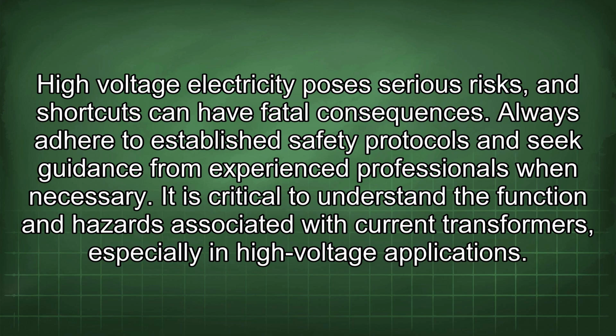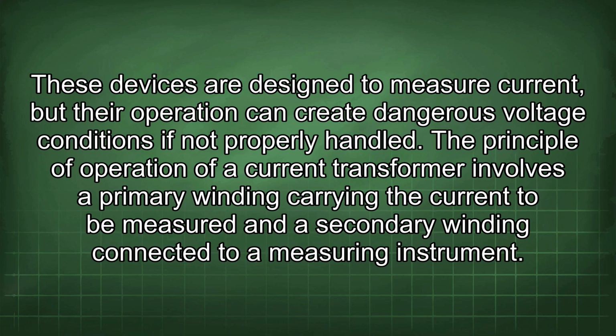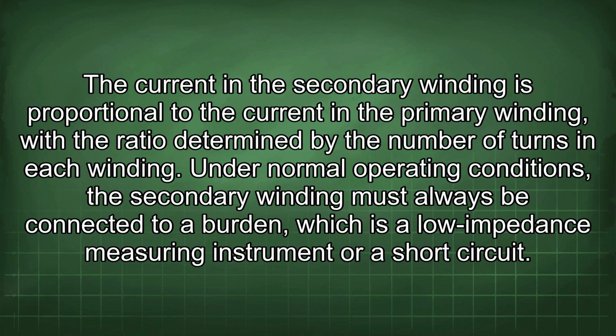It is critical to understand the function and hazards associated with current transformers, especially in high-voltage applications. These devices are designed to measure current, but their operation can create dangerous voltage conditions if not properly handled. The principle of operation of a current transformer involves a primary winding carrying the current to be measured and the secondary winding connected to a measuring instrument. The current in the secondary winding is proportional to the current in the primary winding, with the ratio determined by the number of turns in each winding.